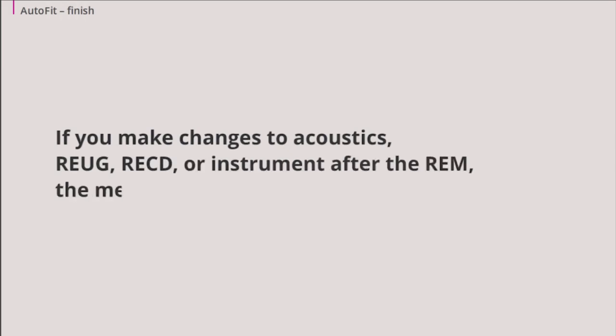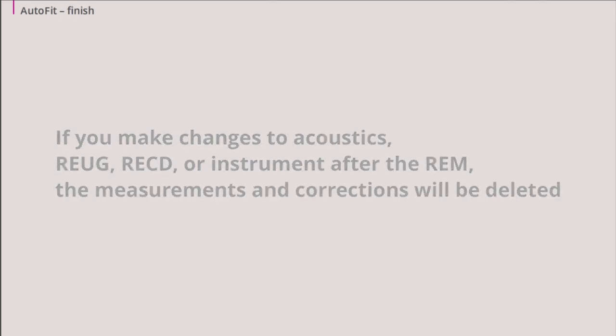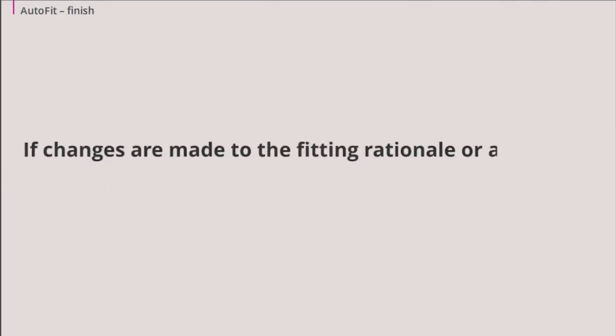If you make changes to acoustics, REUG, RECD, instruments, or age after the REM, the measurements and the REM AutoFit corrections will be deleted. If, on the other hand, changes are made to the fitting rationale or the audiogram, the measurements and the corrections will stay.